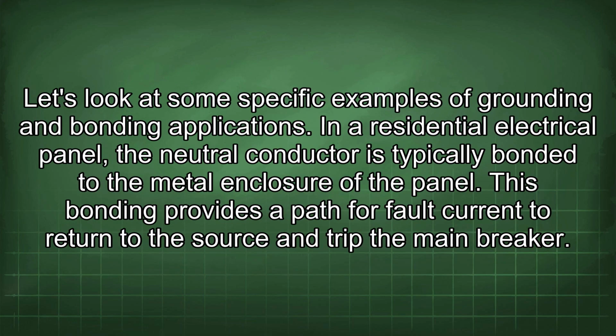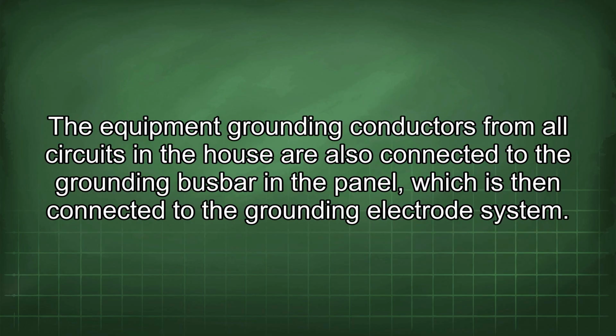Let's look at some specific examples of grounding and bonding applications. In a residential electrical panel, the neutral conductor is typically bonded to the metal enclosure of the panel. This bonding provides a path for fault current to return to the source and trip the main breaker. The equipment grounding conductors from all circuits in the house are also connected to the grounding busbar in the panel, which is then connected to the grounding electrode system.